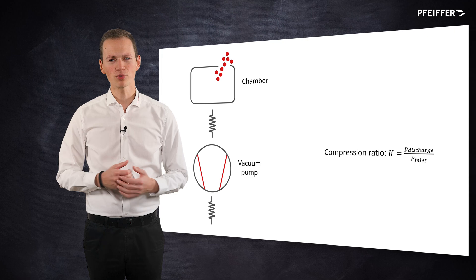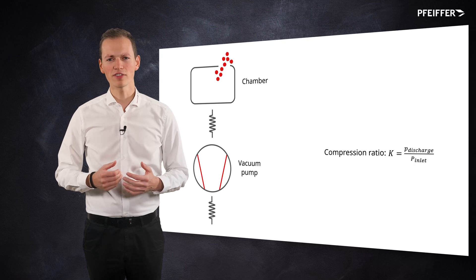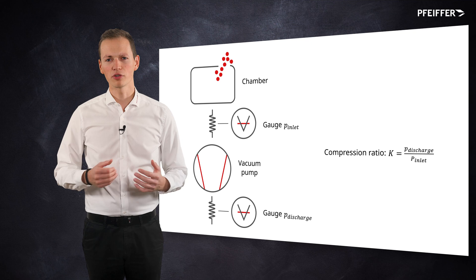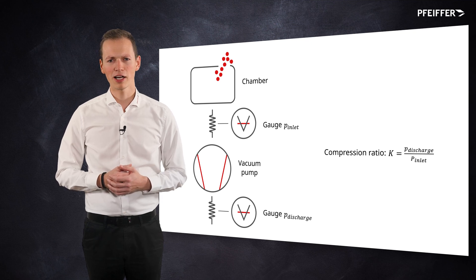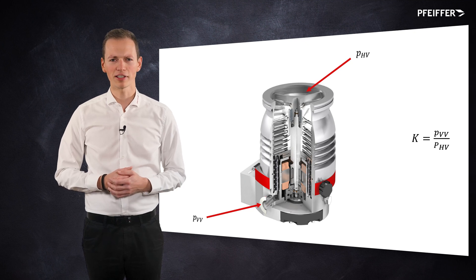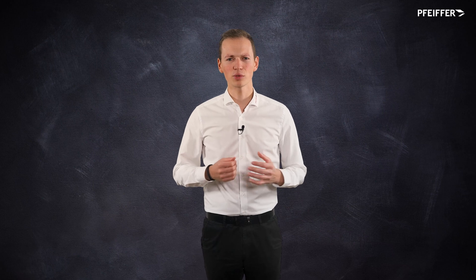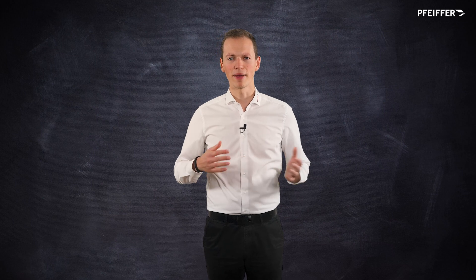A compression ratio is the ratio of a discharge pressure to intake pressure of a vacuum pump. For turbo molecular pumps in particular, it is the ratio of the pressure measured at the fore vacuum flange to the pressure measured on the high vacuum flange. The compression ratio of a turbo pump is measured in practice by increasing the backing pressure through gradually introducing a gas into the fore vacuum line while measuring the resulting high vacuum pressure.